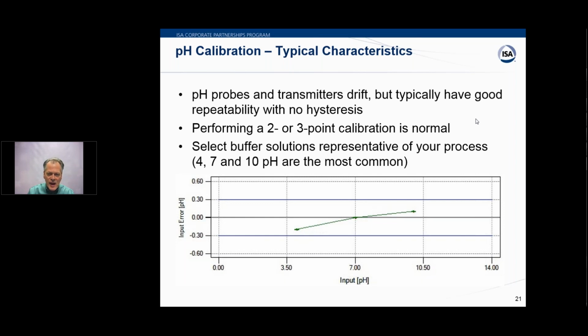But when we talk about calibration, one thing about pH probes and the associated transmitters is, they may drift, they may go a little high, get a little low, but during testing, they really have good repeatability and no hysteresis. So you don't need to do an up-down test. Really checking it at low, medium, and high, whichever, it's going to give you the same results. Also, Ian mentioned cleaning. Obviously, you might want to do an as found prior to cleaning, and then after you do your cleaning procedure, you can make adjustments and then demonstrate an as left change for all that work.